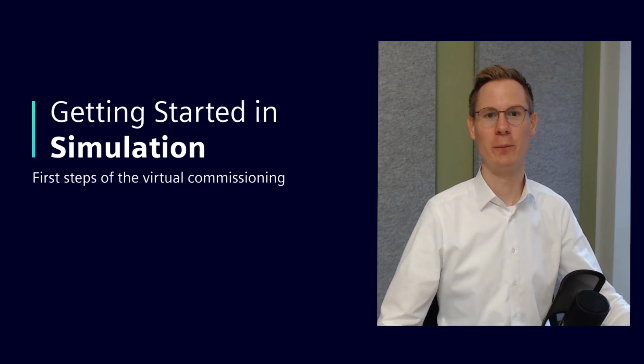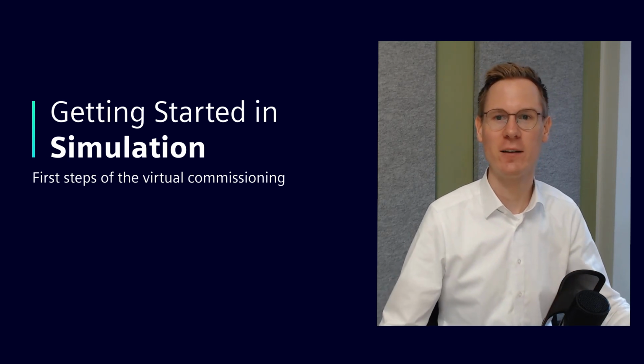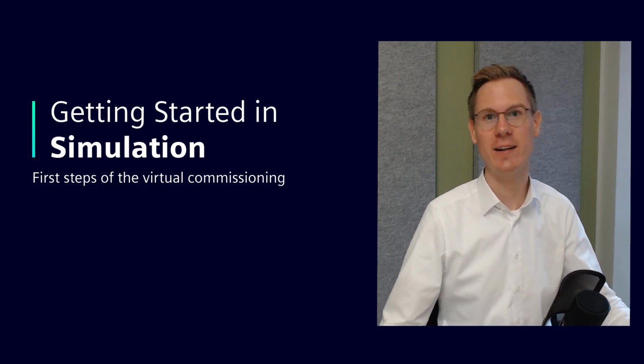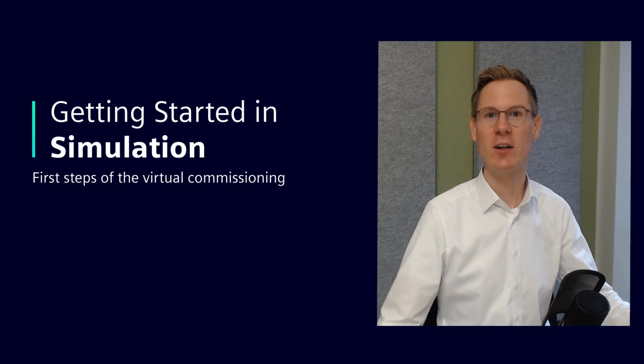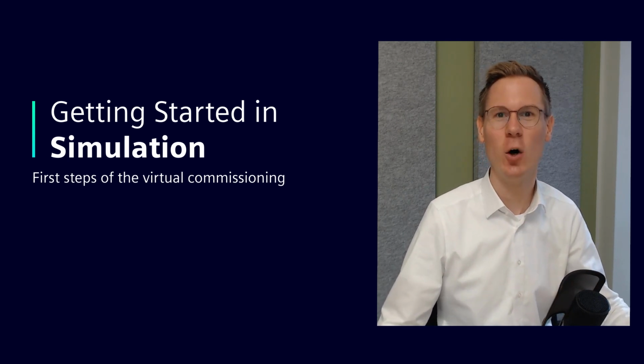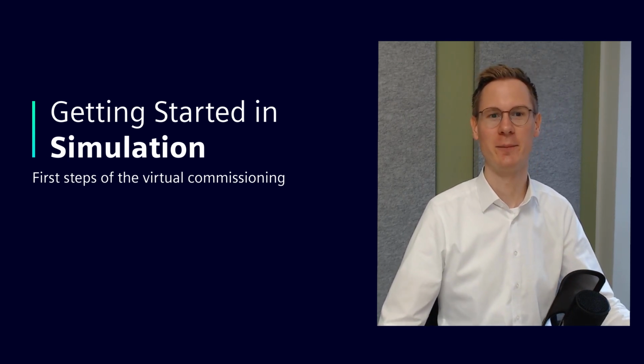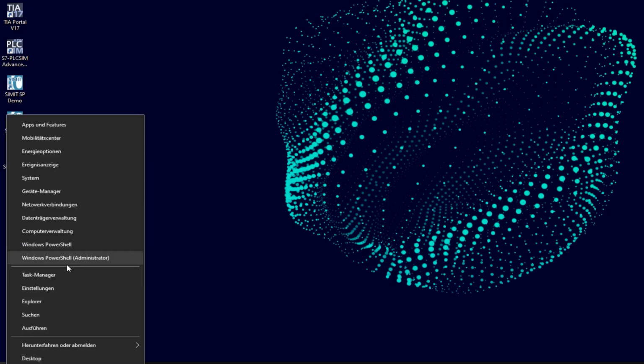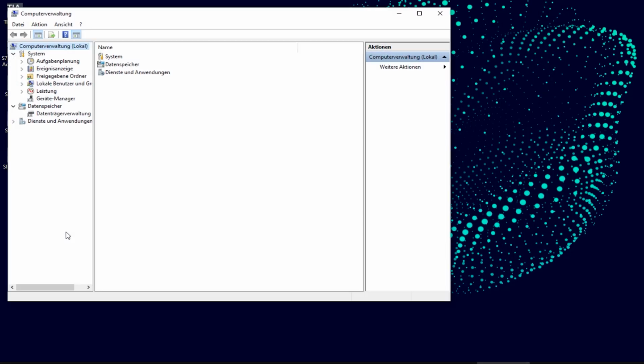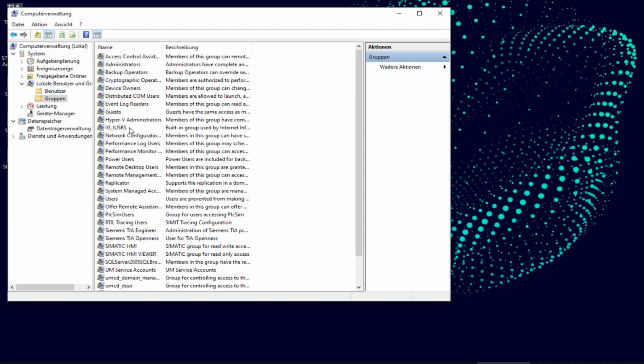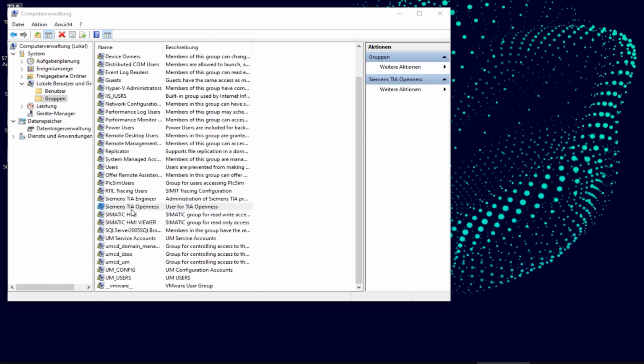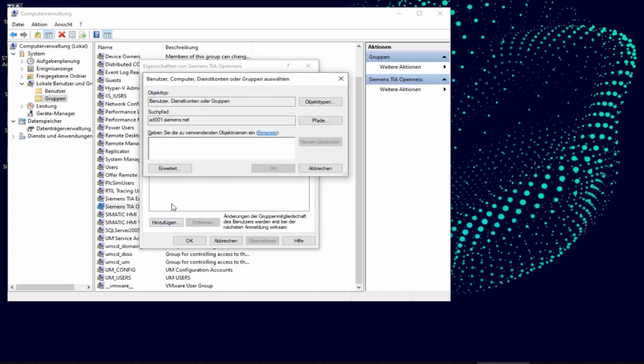Now there is one setting missing. In order for SIMIT to access TIA portal to create the PLC interface in the simulation, the current Windows user must be configured as a TIA Openness user. For this, I open the computer administration, local users and groups, and I add myself as TIA Openness user. You can also find the link to this procedure in the video description.